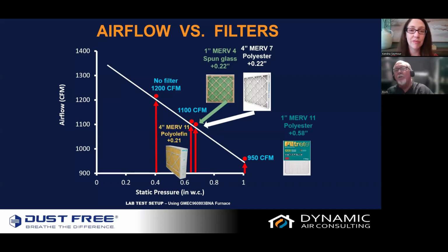So this is a 4-inch, also a MERV 11, and its static resistance is 0.21. Now we're in a decent operating range, but notice it's made out of polyolefin, a different material. One caveat about these different materials is that polyolefin will react negatively to UV light. If you have a UV light in your system, and I've seen them in the darndest places, that can be a discussion for a different day, but they will deteriorate that material. Polyester holds up a little better.